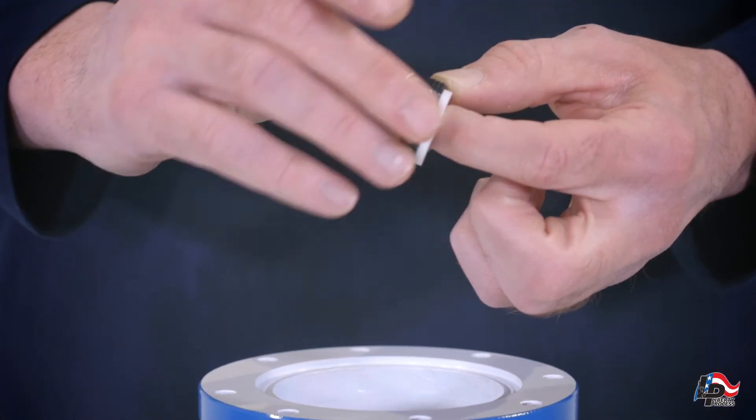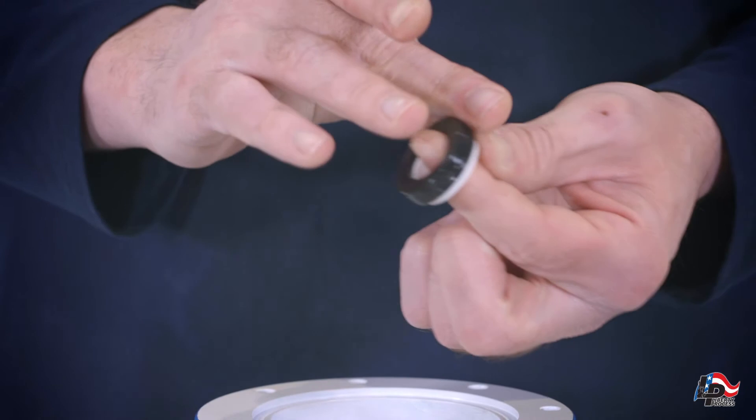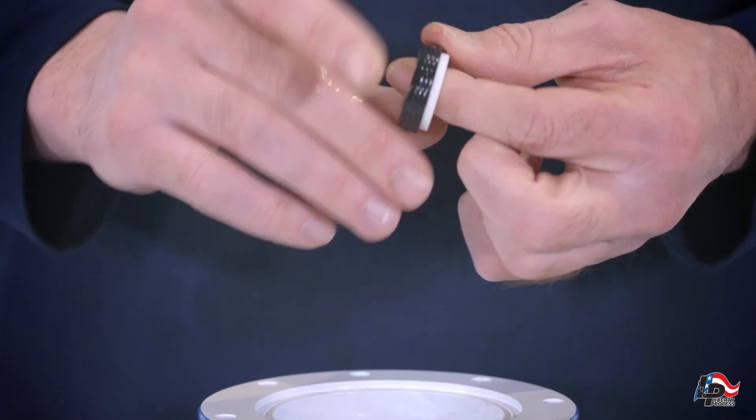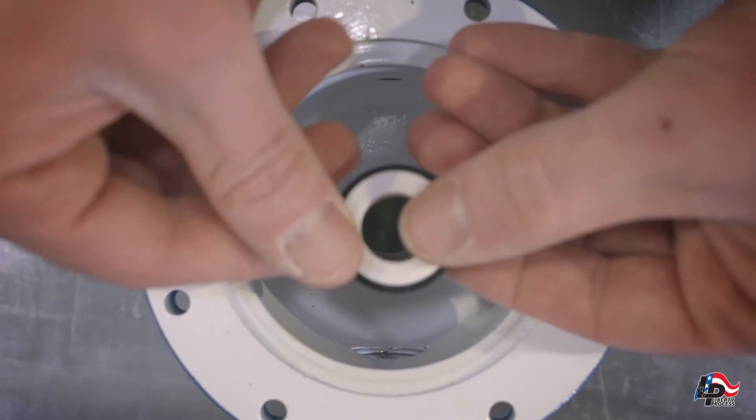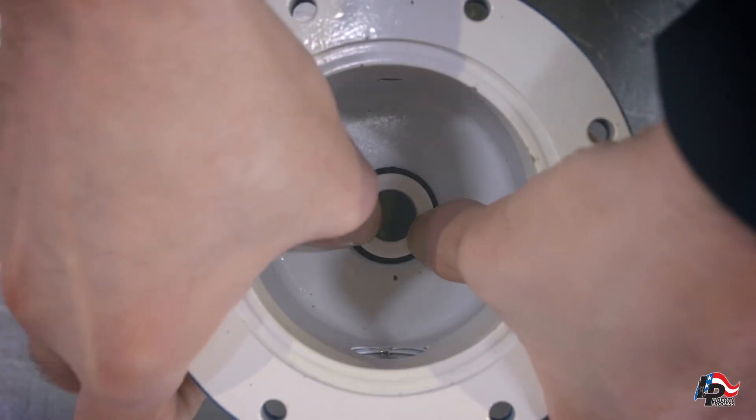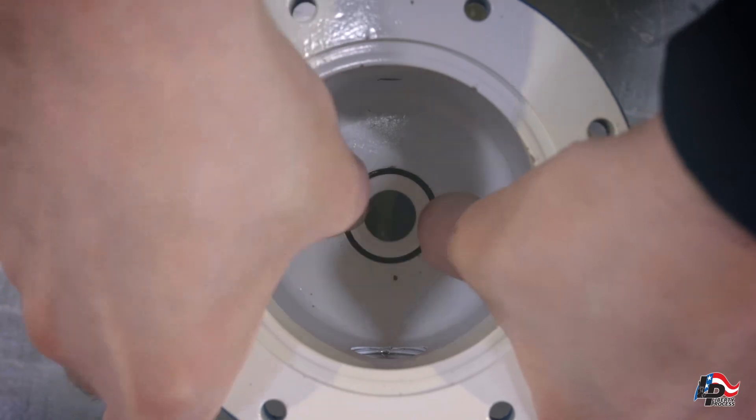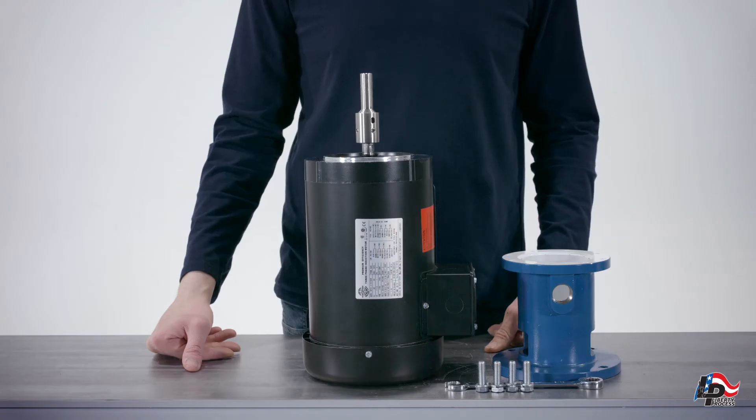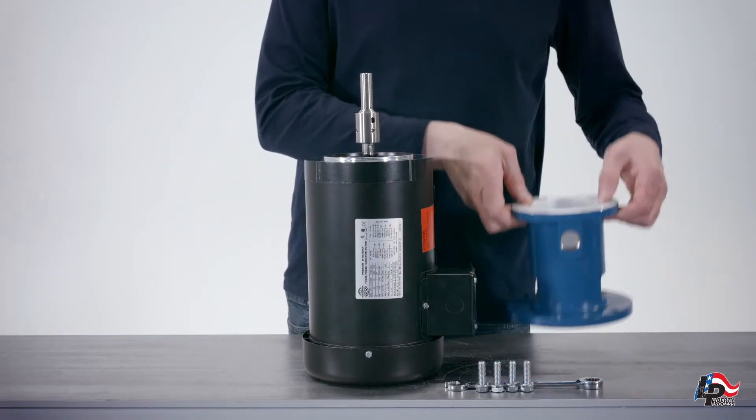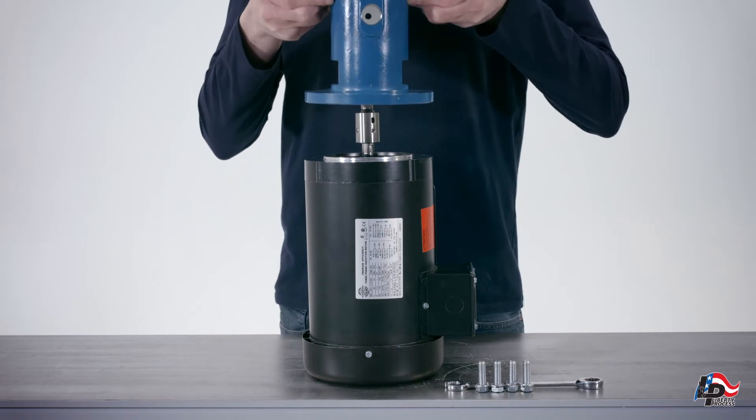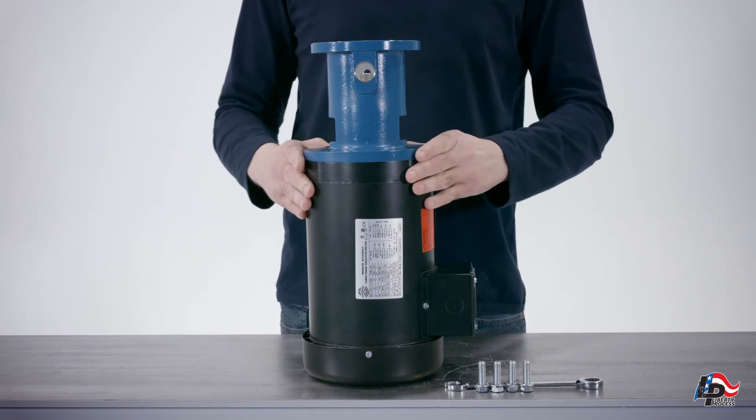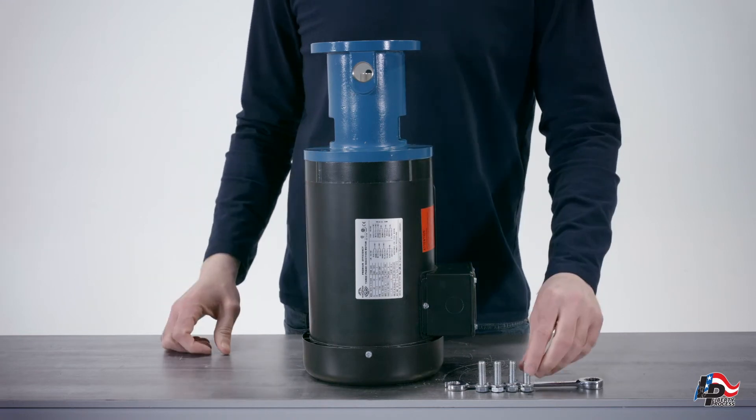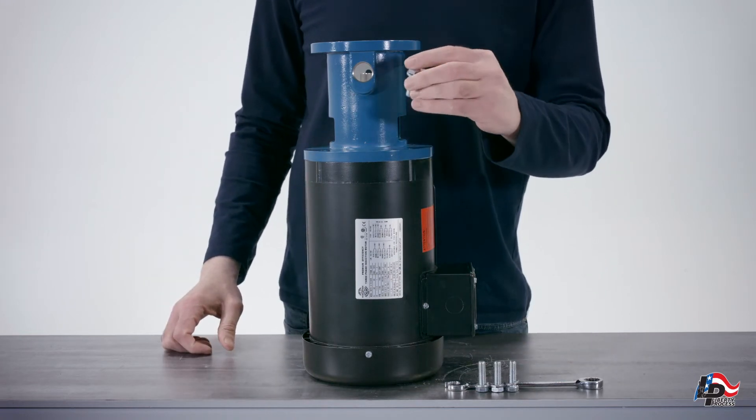Lubricate the outer diameter of the seal stationary face with liquid soap. Using your thumbs, gently press the stationary face of the seal into the discharge casing. Install the discharge casing onto the motor, taking care not to damage the seal on the stub shaft. Tighten the discharge casing onto the motor using the four 9-16-inch bolts.